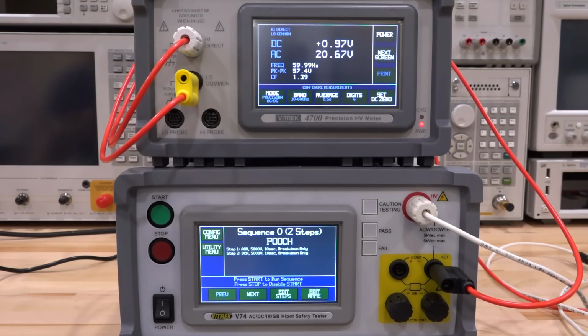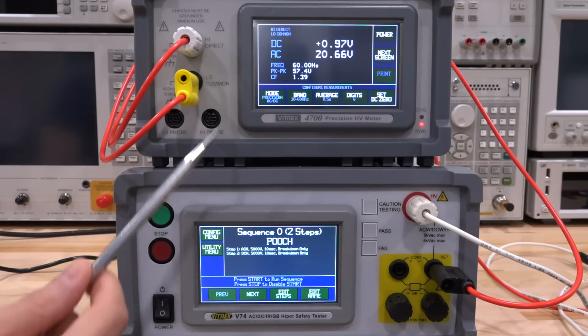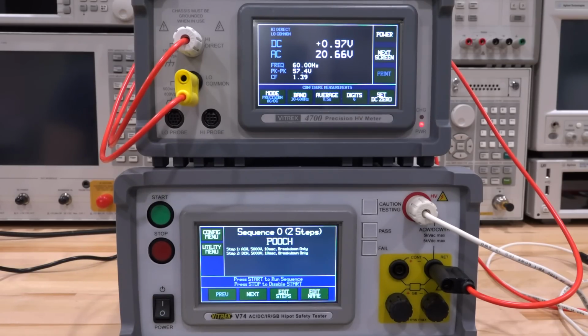This can be very helpful for safety reasons. For example, you may have an instrument that the user is holding, and that user is plugging this instrument into the wall socket. You want to make sure that if the wall socket has a surge, thousands of volts, that it wouldn't find its way to the end user, or that its devices can actually survive and won't arc over. As a result, these things are sold from many different brands. I have a Vitrek one, the same brand as the multimeter up there. Now, this particular instrument can only apply AC or DC, and we will see why when we do a teardown.